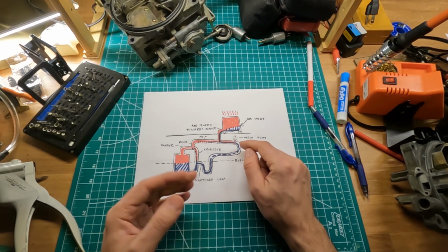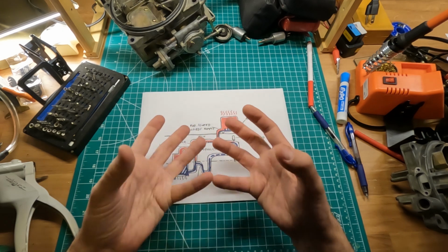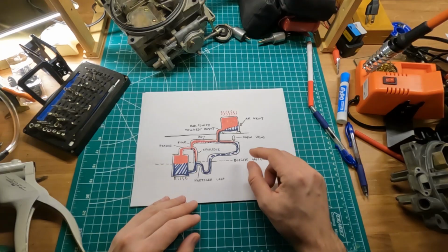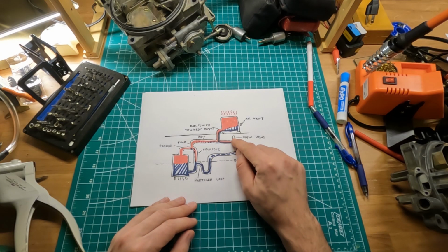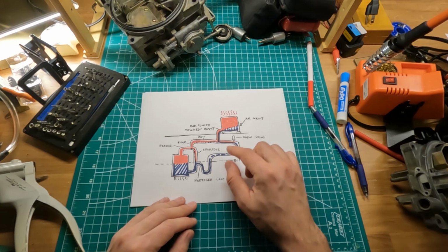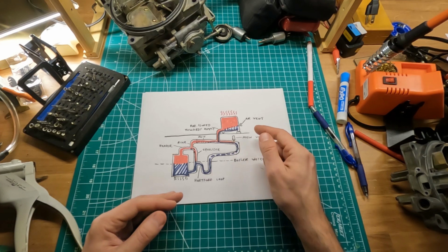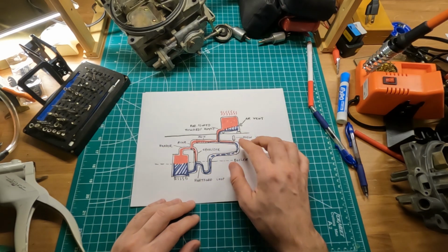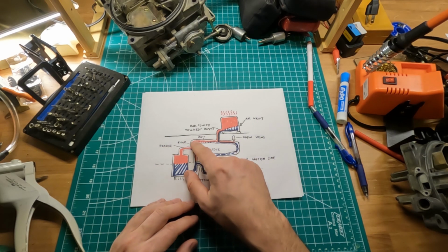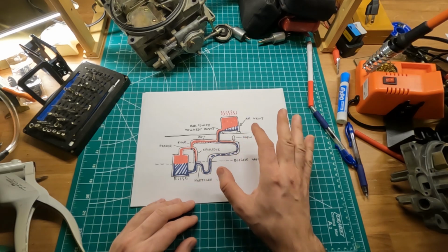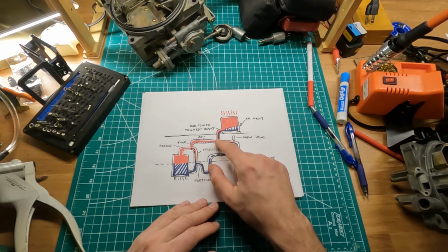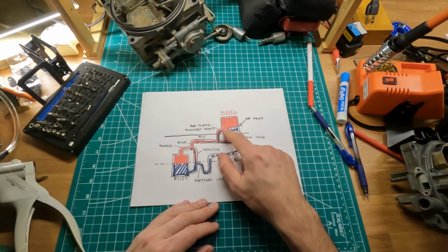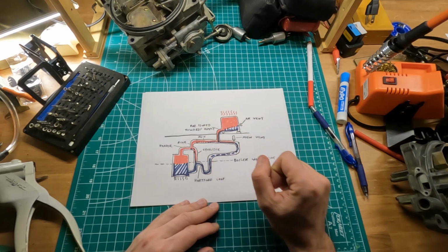So the main vent closes the moment the steam hits it, as in warms it up. The moment the vent detects there is steam hitting it, it closes so that no more air can escape via the vent. Of course, the purpose of that is so that you don't waste this precious steam warming up this basement right here, as opposed to going where it's supposed to. When that happens, the steam finds other ways of going up the pipes, and then finds one pipe right here, and goes up the riser to the one and only radiator that we have in our simplified drawing.